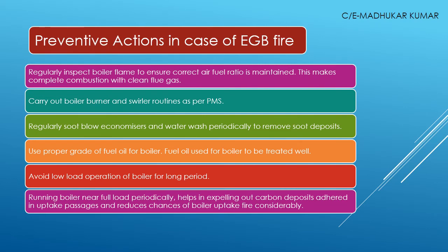Now we will see about the preventive actions for EGB fire. First, regularly inspect the boiler flame to ensure the correct air-fuel ratio is being maintained — this ensures perfect combustion and no carbon residue, giving clean flue gases. Carry out boiler burner and swirler routines as per the PMS to maintain perfect operational conditions and complete combustion, resulting in clean flue gases without soot. Regularly soot blow the economizer and water wash periodically to remove soot deposits — if deposition has already occurred, soot blowing or water washing will remove it.